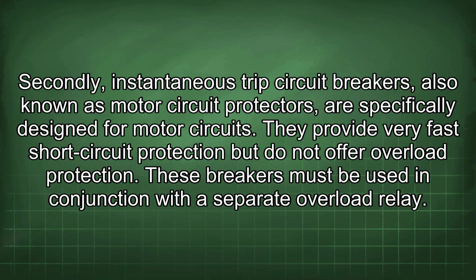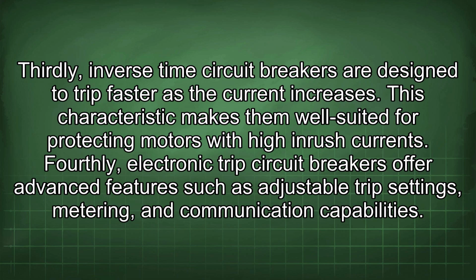They provide very fast short-circuit protection but do not offer overload protection. These breakers must be used in conjunction with a separate overload relay. Thirdly, inverse time circuit breakers are designed to trip faster as the current increases. This characteristic makes them well suited for protecting motors with high inrush currents.